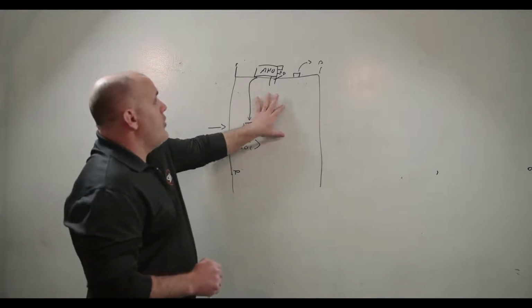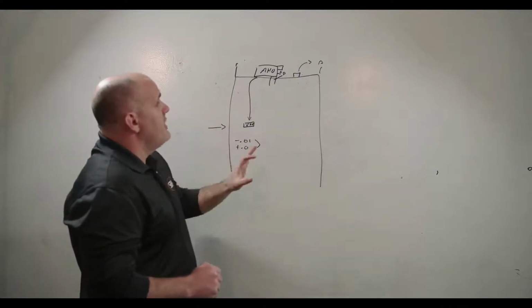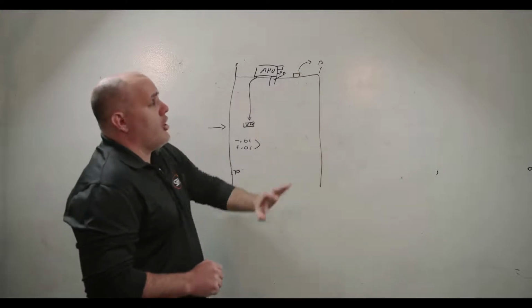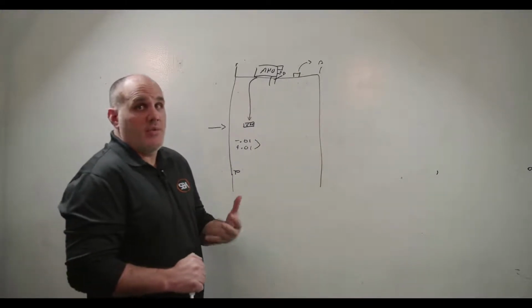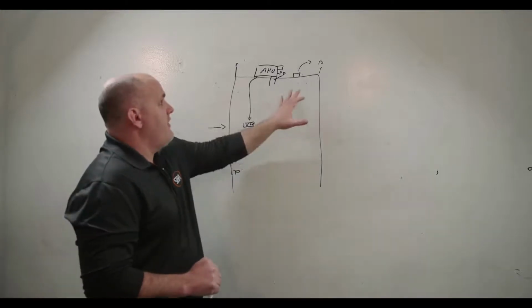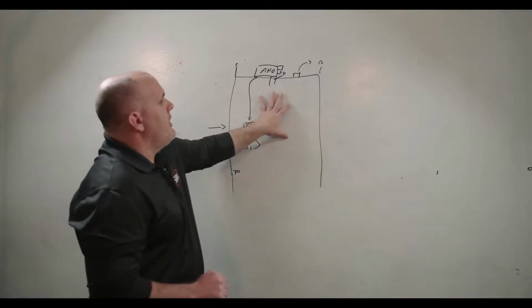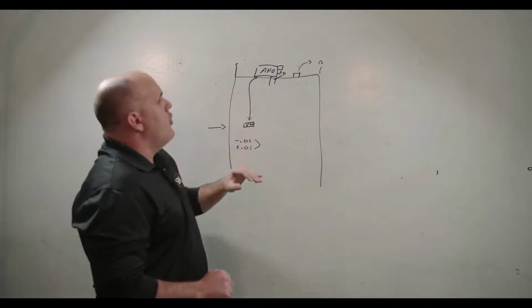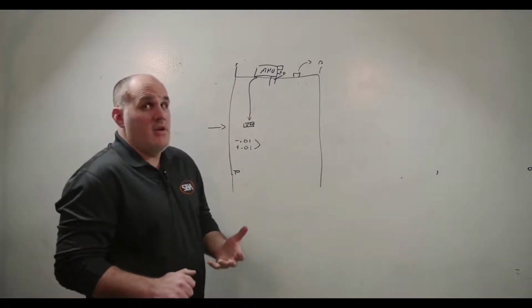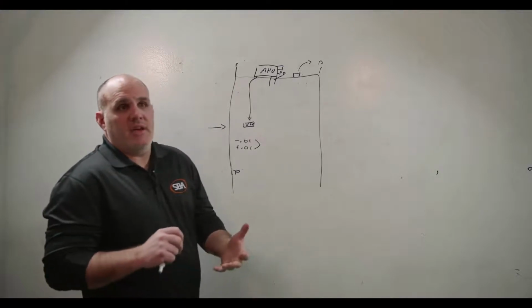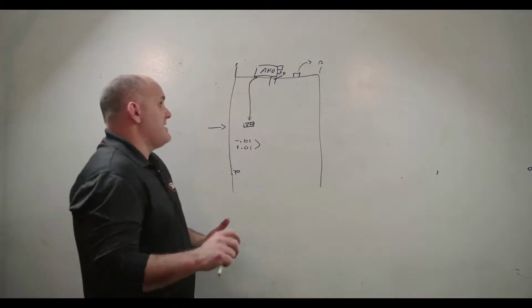Most of the time, though, we're concerned with building static pressure, and we will drive our relief fan to drive that building static pressure. We will control building static pressure off of a variable relief, or we will have an offset, or we will have that signal matching, or we'll just have a static setting on our exhaust that's been kind of designed by Test and Balance, that setting.